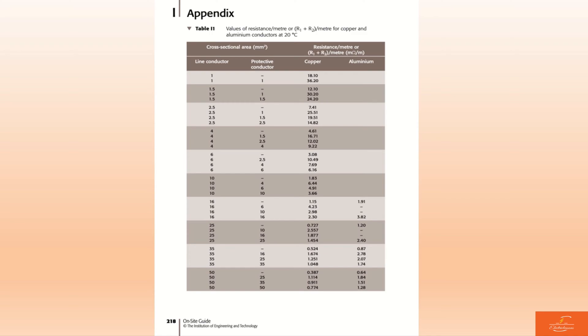What do you have in this chart? We have the cross-sectional area, we have the line conductor which is also known as R1, and we also have the protective conductor which is also known as R2. We also have a resistance per meter or R1 plus R2 per meter for all these conductors in this chart, and the resistance is in milliohms per meter.